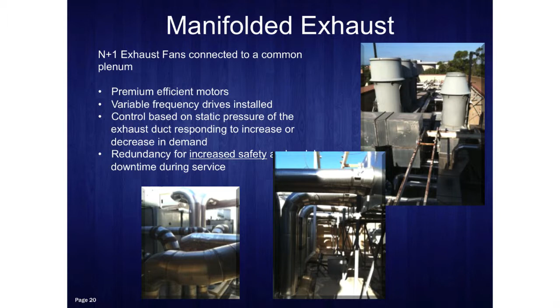Manifolded exhaust. We heard from Harvard this morning that they definitely get this and understand it. Unfortunately, you go campus after campus and you still see the single exhaust fan being served by the single hood. You don't have an N+1 design. Right there's a safety question. What happens when that belt breaks and somebody's working in that hood? Especially if they're using something that could be exposed to them very, very quickly, where they're depending on that hood to provide that safe area to work in.